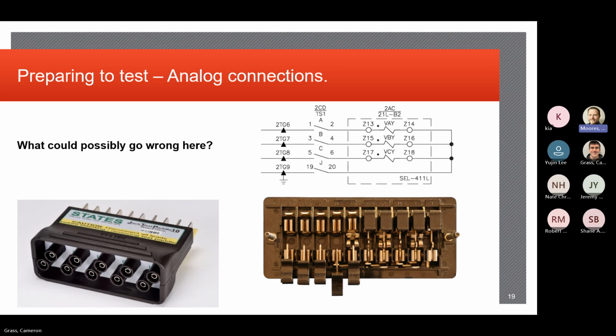So what I mentioned a little earlier with the test switch, the test plug on the left would slide into those test ports on the top of that FT switch with all those blades open. But that's going to actually put the test set plugged into those odd numbers, which is looking out into the field, not the relay. We want it to look into the relay. So what Cam's pointing out is that test switch is basically hooked up backwards. Right, something to worry about.